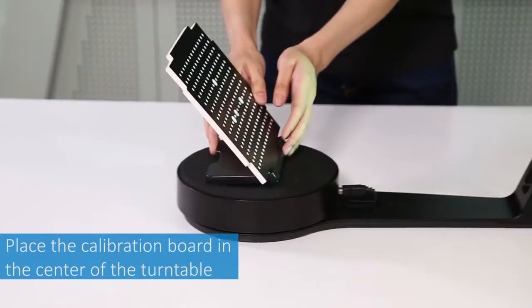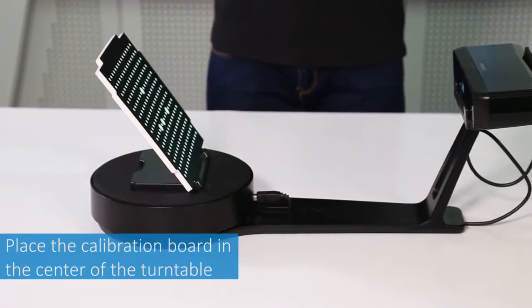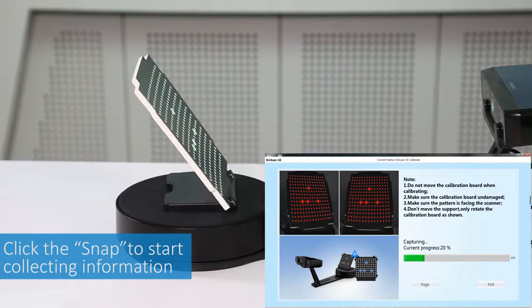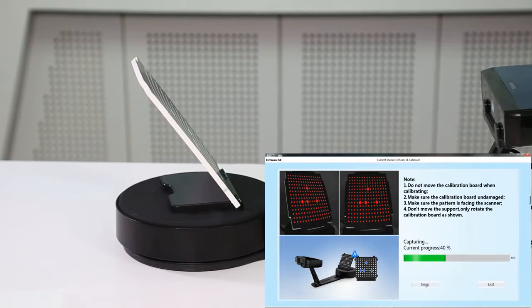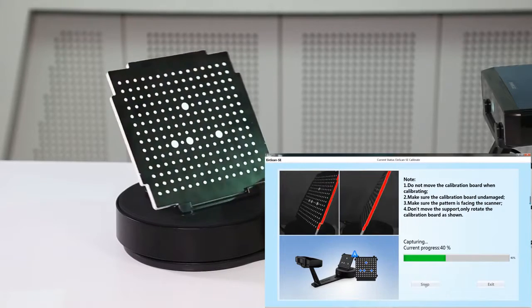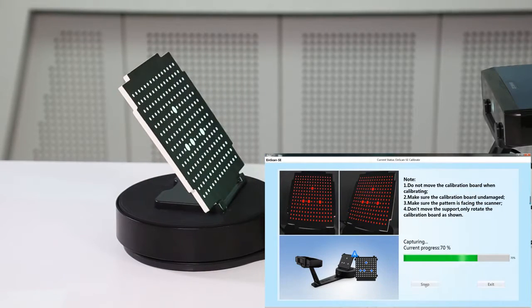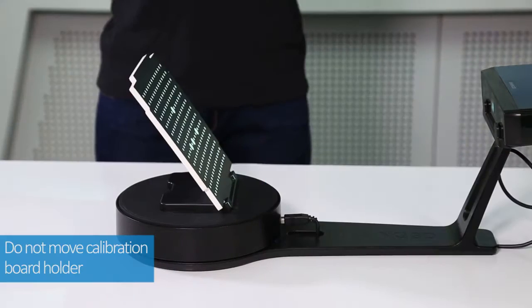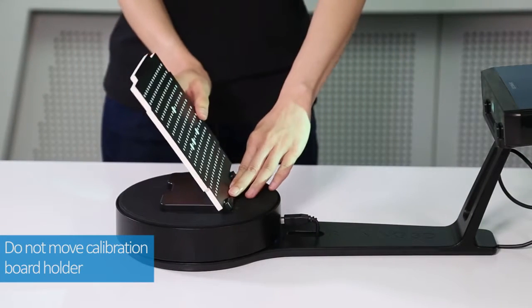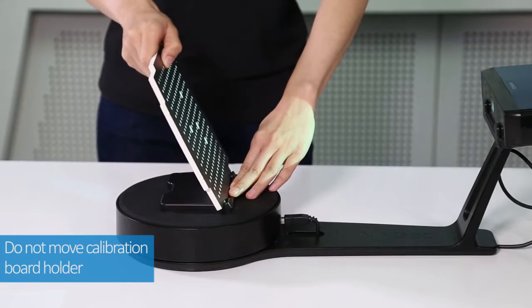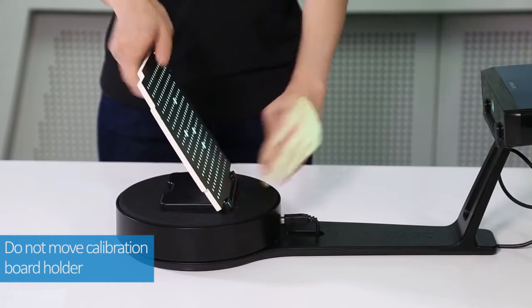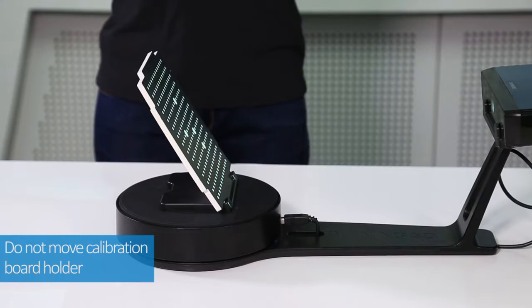Place the calibration board in the center of the turntable. Click the snap button to start collecting the calibration board information. After the calibration board information collection is completed for the first position, the software will automatically prompt for the collection of the second position. Rotate the calibration board according to the prompt. Now remember, only the calibration board is rotated and the calibration board holder should not be moved.